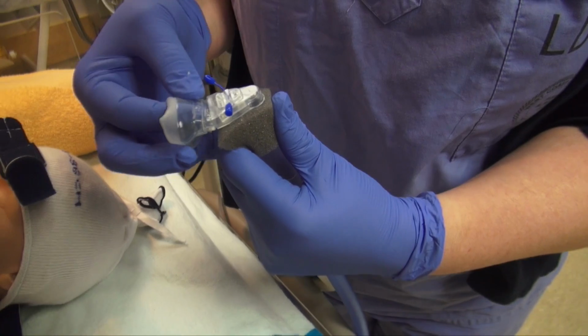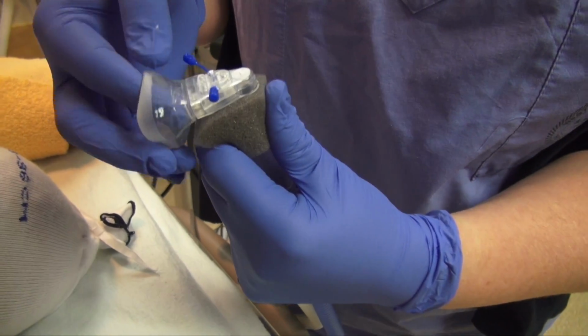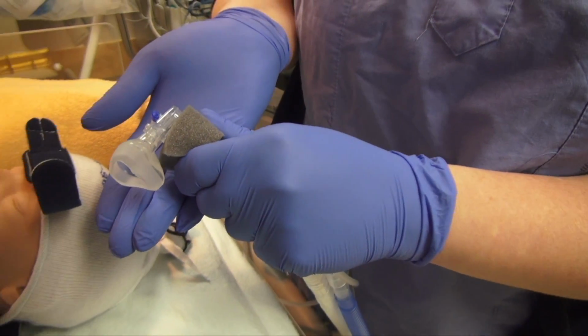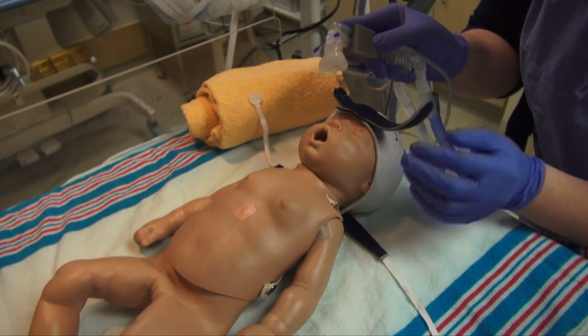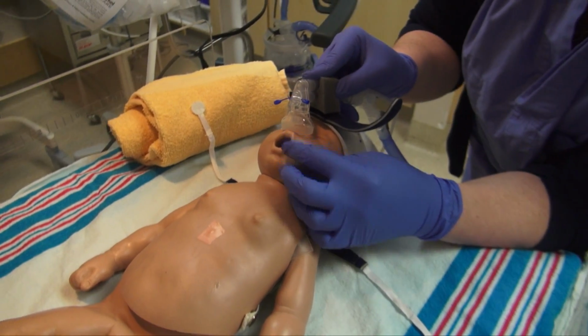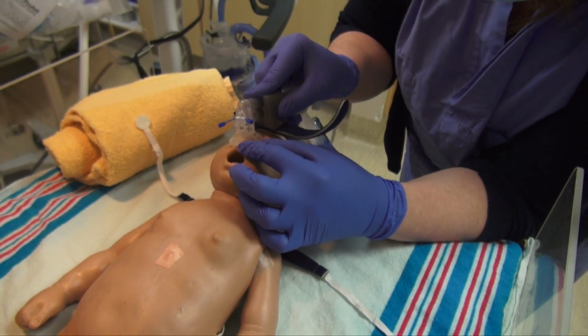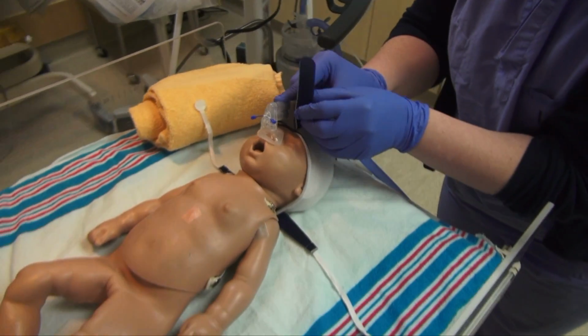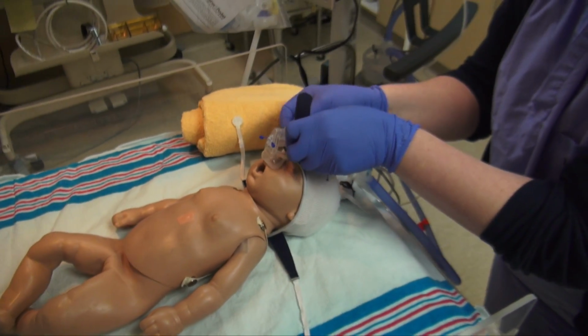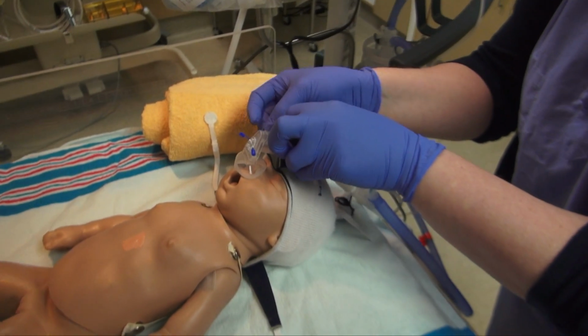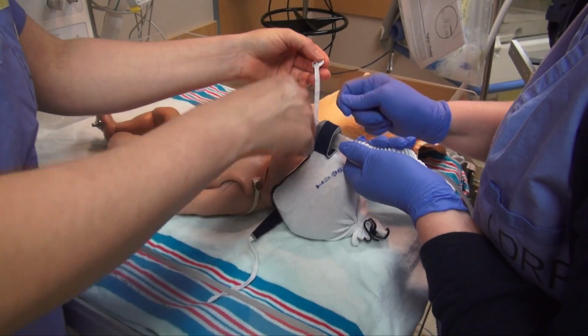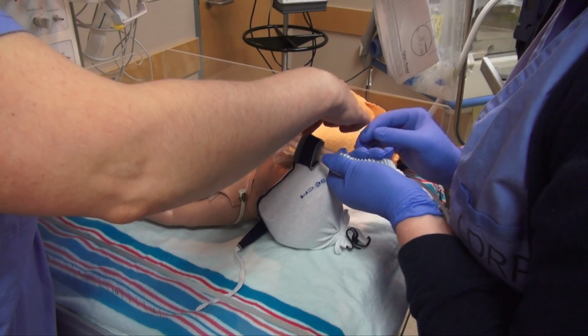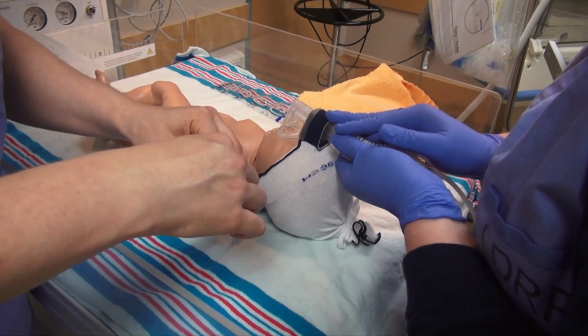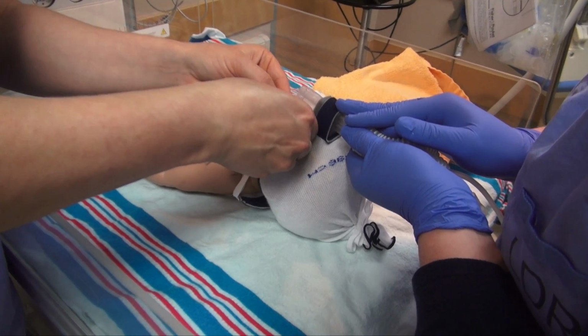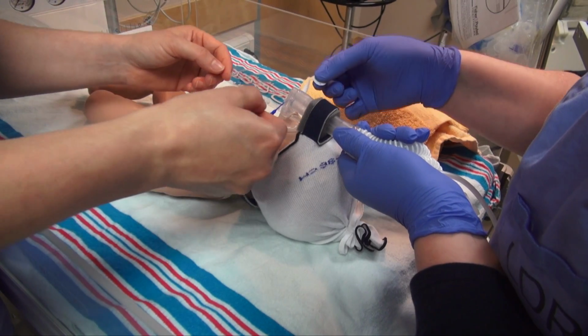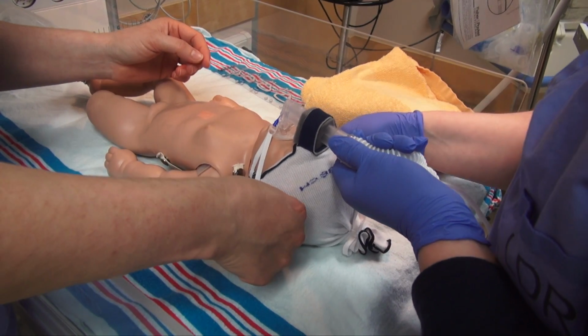Connect the mask to the nasal tubing, ensuring that it is fully inserted. Connect the patient by placing mask around nose. The mask should sit comfortably around the patient's nose. It must not occlude the nostrils or touch the septum and should not be over the lip or over the eyes. Hook the clips from the side straps of the bonnet to the glider. Pull both straps at the same time for central positioning.